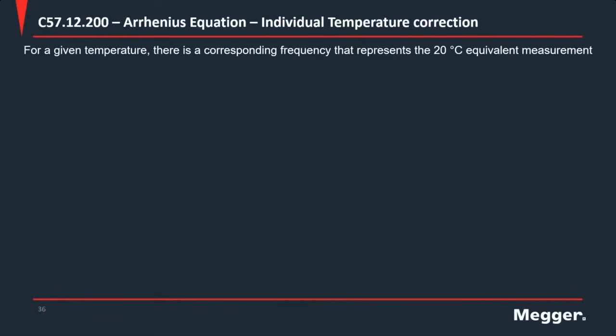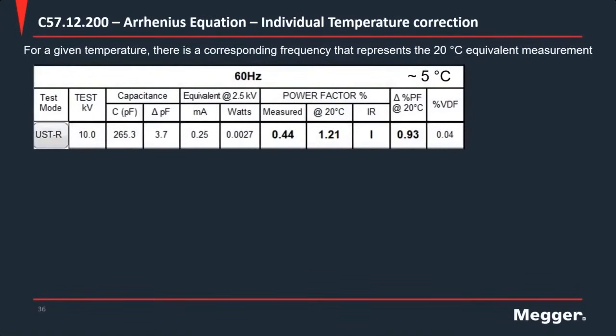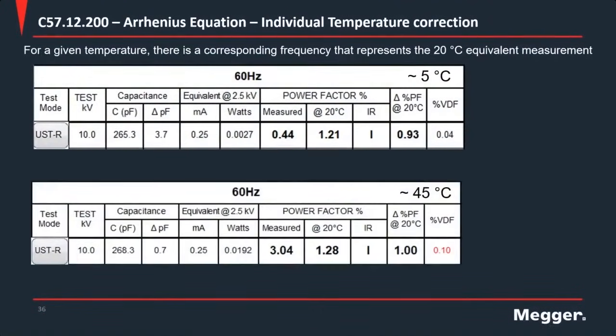So here, when we apply this to that same bushing, and when we tested at either 5 degrees C or 45 degrees C, we notice that using this Arrhenius equation or individual temperature correction method, it gets us a lot closer in values than when we use the temperature correction tables. So just know that there is a better way to perform temperature correction, and it is called the Arrhenius equation, or the individual temperature correction, here at Megger. And this will allow you to make the best informed maintenance decisions for your assets.